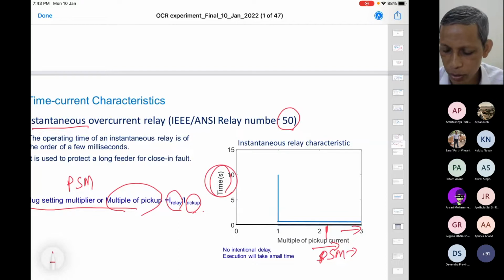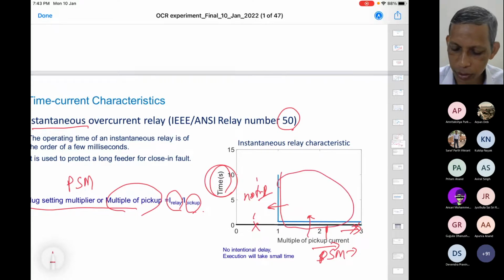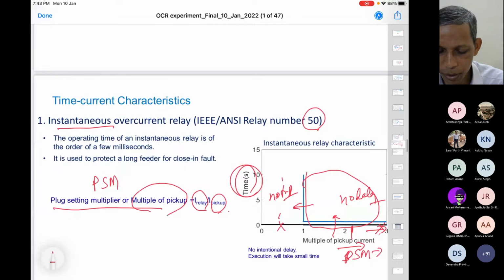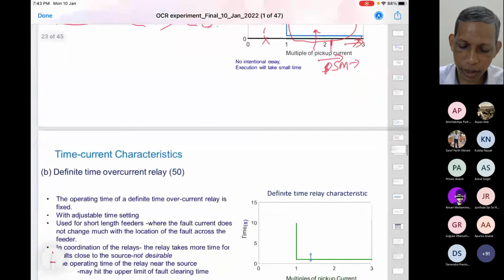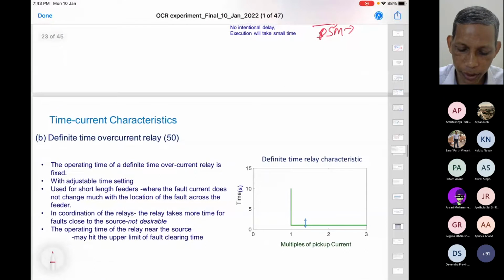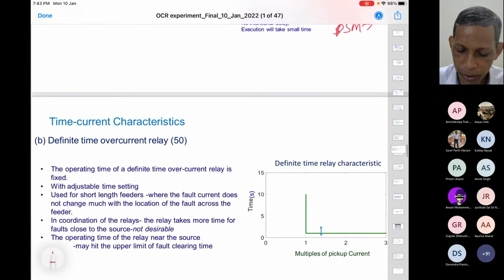So in this case, no delay, instantaneous, and it trips. Anywhere in this region it is tripping, and beyond this there is no trip. Time is very high, infinity theoretically, in the no trip region. But within this region, no delay. So this is the characteristic for 50. Then there is the definite time over current relay. We also call it 50 definite time.